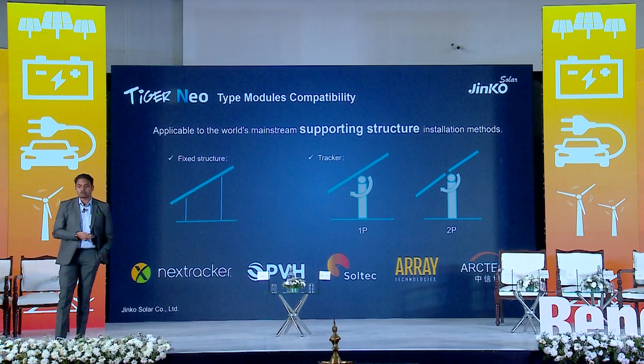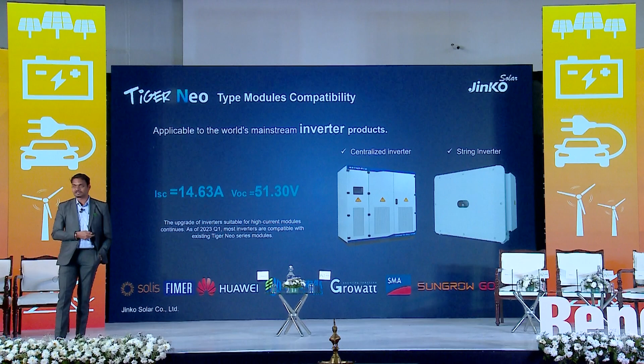On the inverter front, whether you go with a string inverter or central inverter, since we are using 182 mm by 182 mm wafer size, our module's ISC is always less than 15 amps. So you can easily club two inputs to a Y connector into the single input of your MPPT of a string inverter. That definitely reduces your BOS costs on the optimization front, giving you a better advantage on the capex calculation.